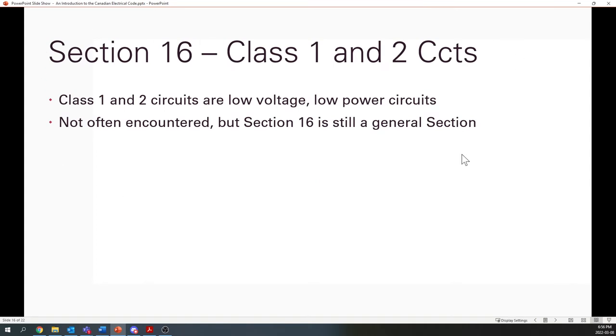Section 16 is low voltage circuits, class 1 and class 2. I have really never used section 16 before. It covers communication circuits, control circuits, where you might have like a wiring from a sensor or some sort of instrumentation in a plant back to a PLC or some other sort of controller.